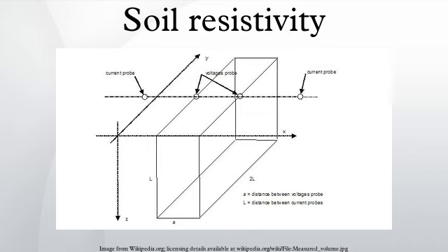Soil resistivity variability. Electrical conduction in soil is essentially electrolytic, and for this reason the soil resistivity depends on moisture content, salt content, and temperature. Because of the variability of soil resistivity, IEC standards require that the seasonal variation in resistivity be accounted for in transmission system design. For practical purposes, when there is no other available information, in very cold regions, during the winter, a resistivity scale factor of 5 to 6 times the summer value would be an adequate average.